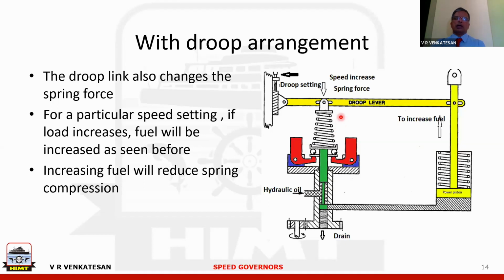In other ways, you are telling the governor that as I keep increasing kilowatt, you don't have to maintain 60 hertz. You can allow the frequency to come down by a small amount. So the droop in a governor is not a defect in the governor. It is a deliberately set feature. So when we want, we will allow the governor to run at reduced speeds as the load increases more and more. So that is how this mechanism is.